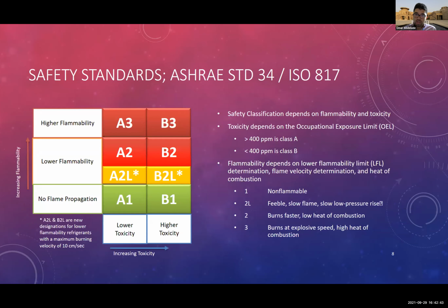Safety is usually defined according to the ASHRAE standard 34 or ISO standard 817. And a quick summary of how these work is in this table here. Basically, we define the toxicity and the flammability. If it is safe and non-toxic, we call it class A. The borderline between class A and class B is the occupational exposure limit. What is the allowable exposure limit? If we can release more than 400 ppm in the room and we still think that the refrigerant is not going to cause a toxic environment, then it is class A. And if 400 ppm or less is going to cause a toxic environment, then we call it class B.